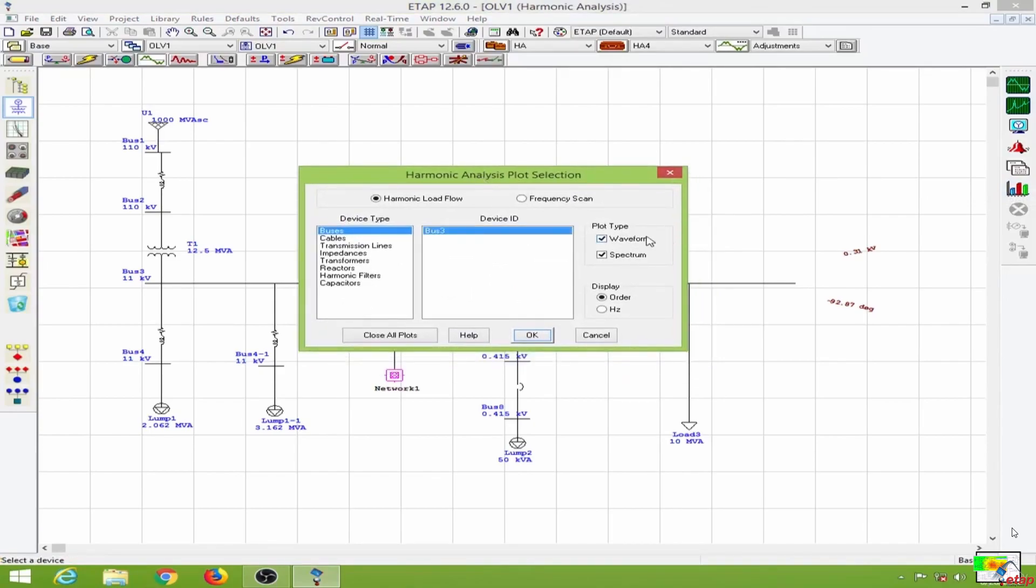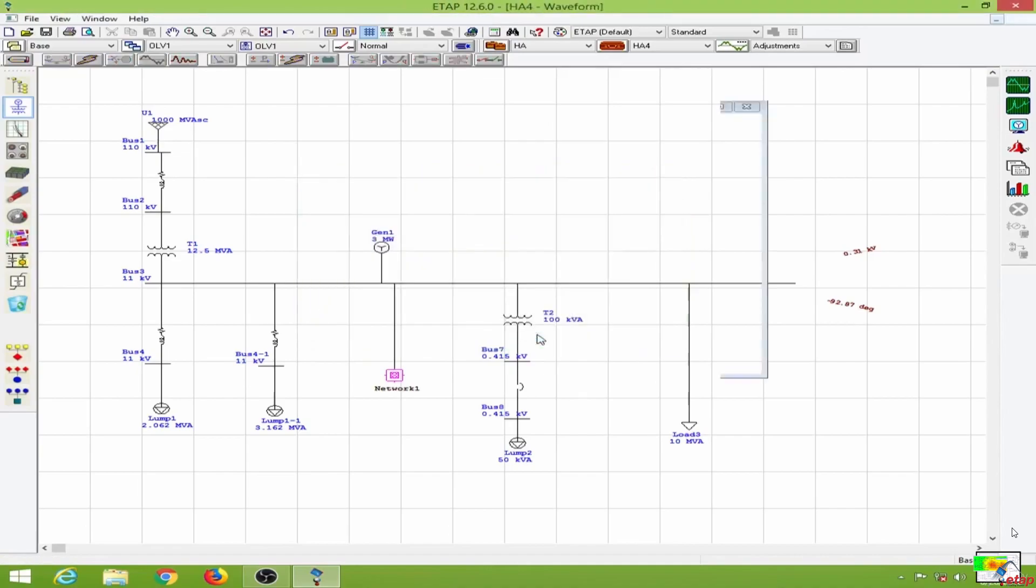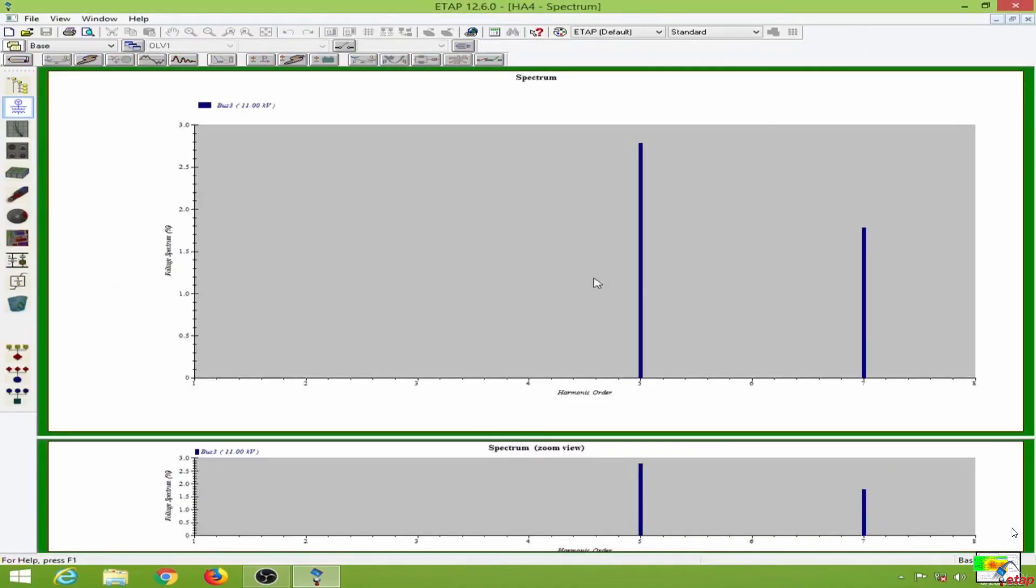Now let's go to plot. I will select the waveform and the spectrum for bus 3. As you can see, the fifth order harmonic magnitude is about 2.8.